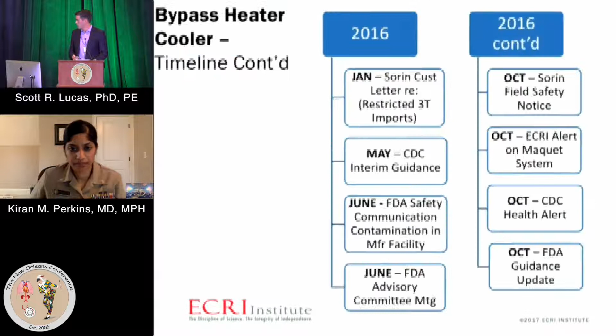All right, so I wanted to dig in a little bit on the June 2016 FDA communication, because that's the line in the sand. That September 2014 date we see is the reason for that, because of testing on the manufacturing plant line that identified the M. chimera, and then identifying it later as a point source for the infections in Europe. So we see that September 2014 date really is the line in the sand, and this is why. So we have devices that were manufactured prior to September 2014 in the marketplace that are theoretically at a higher risk of contamination and aerosolization to a patient.